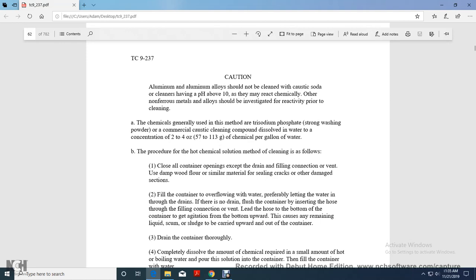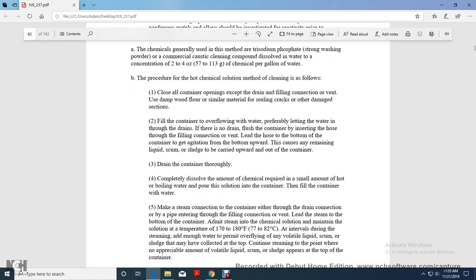Generally use the trisodium phosphate strong washing powder method. Commercial caustic cleaning compound is dissolved in water at a concentration of 2 to 4 ounces of the chemical per gallon of water. The procedure of the hot chemical solution method of cleaning is followed. Close all the container openings except for the drain and filling connection or vent, using damp wood or similar material to seal cracks or other damaged sections.